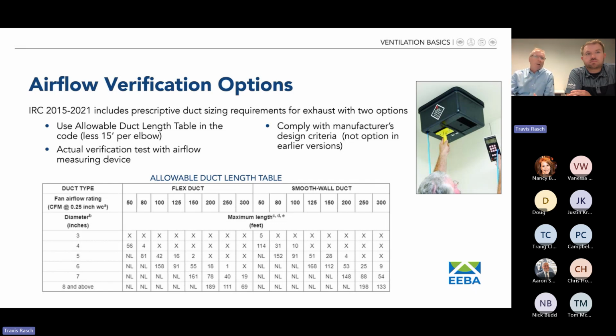Now, it's noteworthy this table has the termination fitting, a roof or wall cap, baked into the numbers, but it does not bake in elbows. So you have to subtract 15 feet for every elbow from the numbers you find in this table. Where you see NL, for instance at 5-6 inch ducting, that means no limit. You can have as much ducting as you want. This is probably the most common way that inspectors or HERS raters check for field verification of airflow. They're going to check the box based on this table, but they also can do a field verification test, as you see in the image in the upper right here, a HERS rater inspector checking it with an actual device, or you can comply with the manufacturer's criteria.